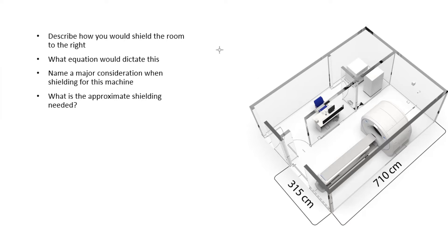The very first thing you would need to do is to ensure that you know that this is a CT unit, and you want to shield this CT room. How you would and the equation are very similar. To begin, you want to find the barrier transmission factor, which we call B.